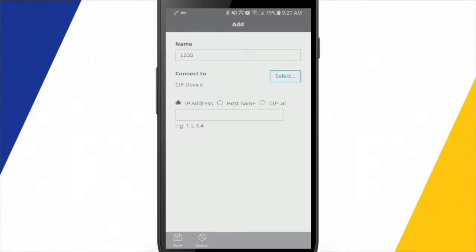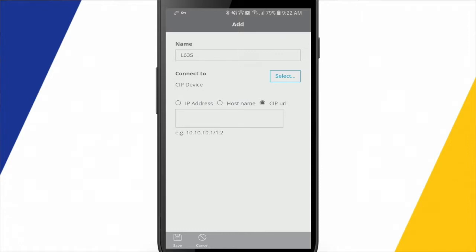And then we have to give it an address to connect to. In the case of a drive, you can leave it just as IP address and type that in. But in the case of a processor, if we're navigating through an Ethernet module, across a back plane, things like that, we actually want to go over and type in a CIP URL.